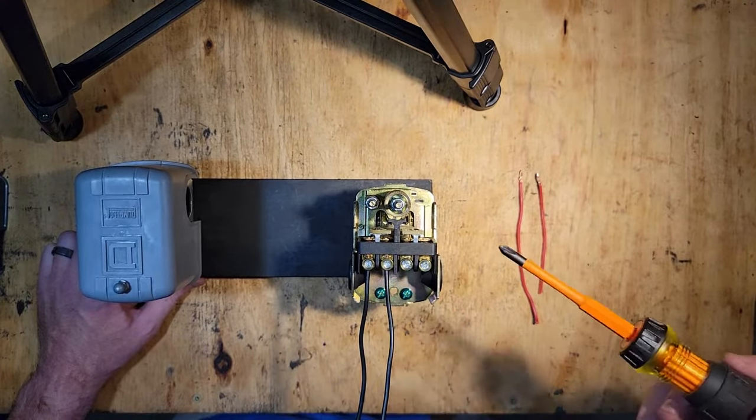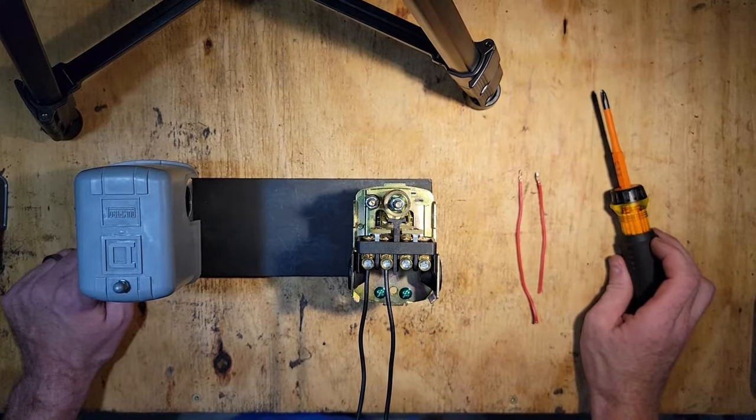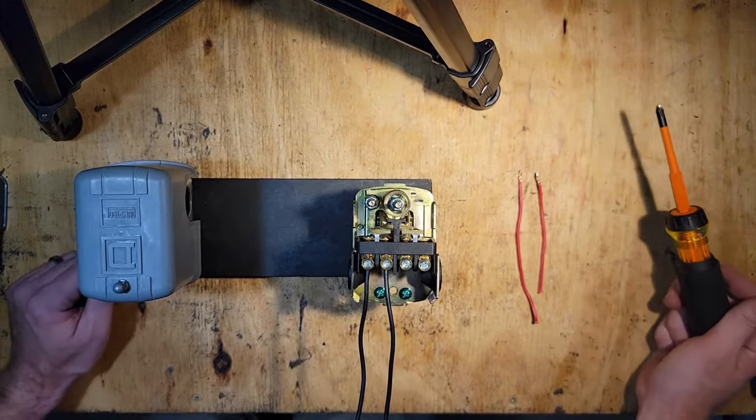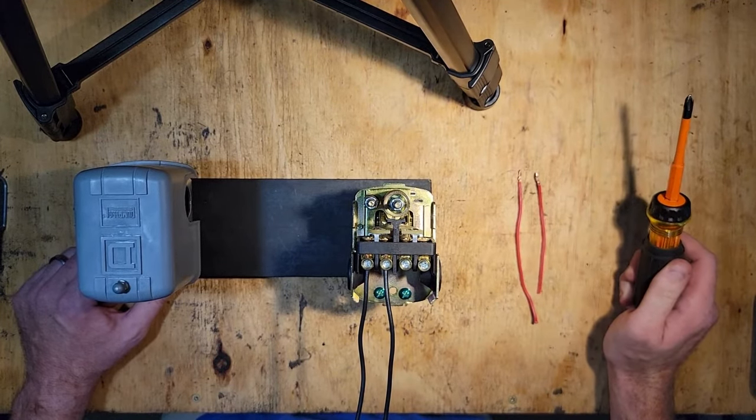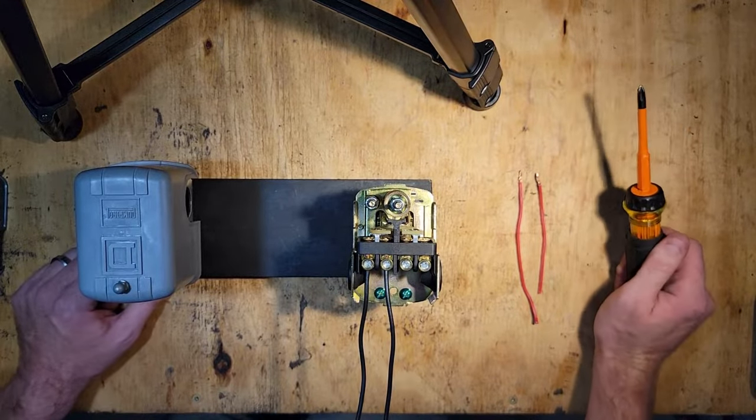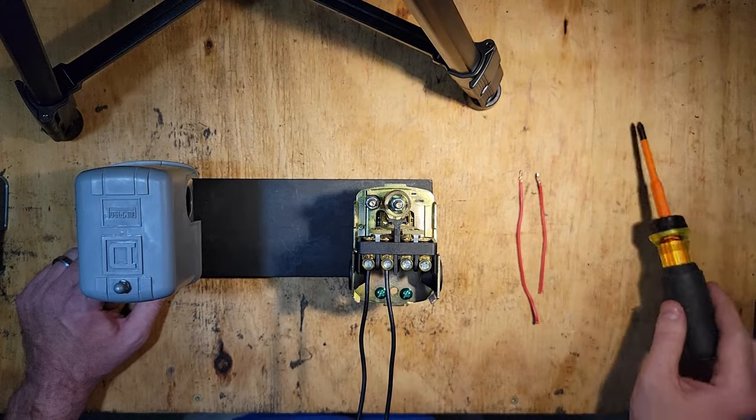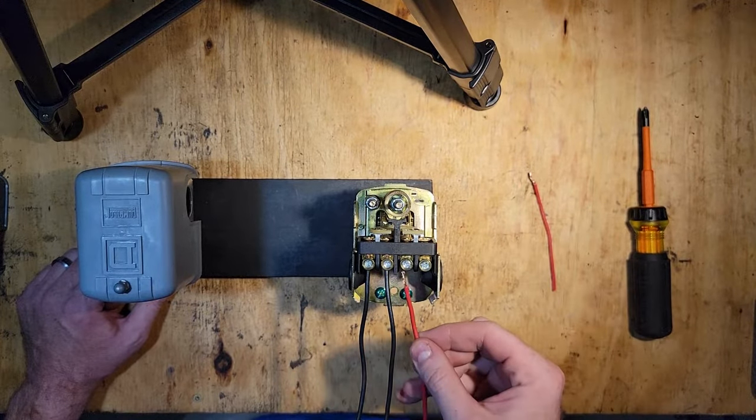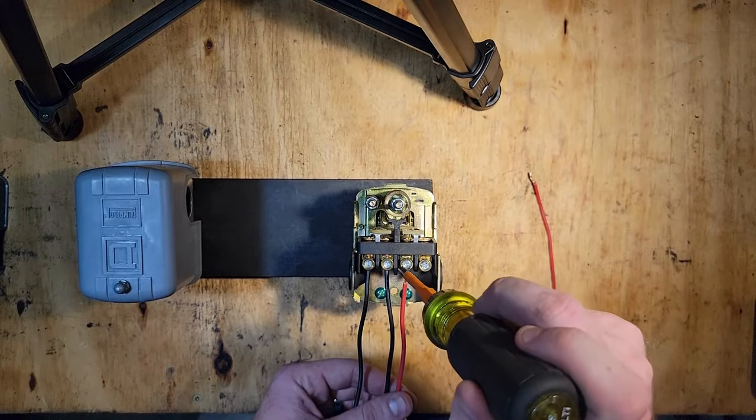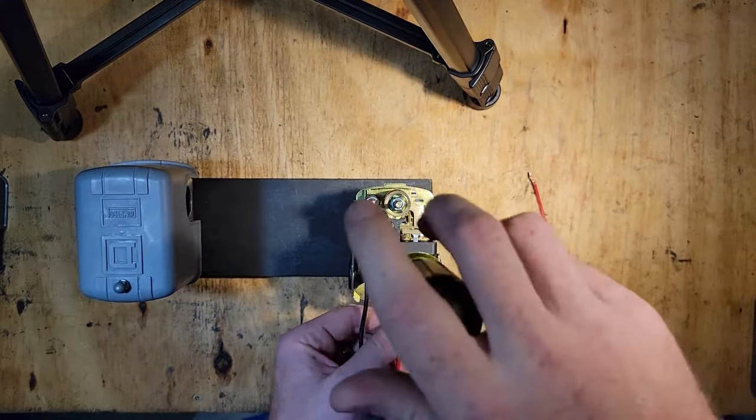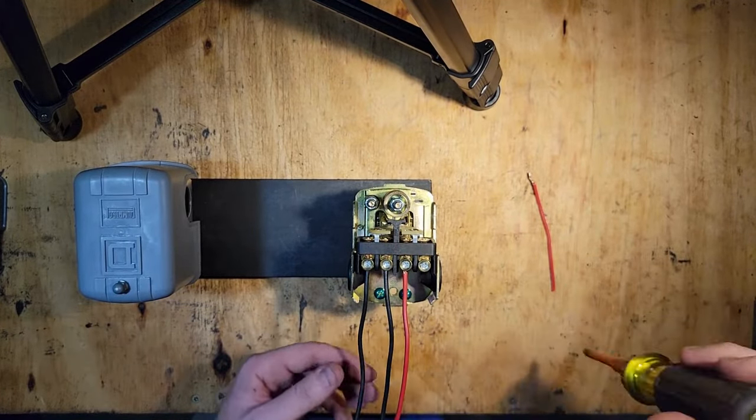Now if you have a control box that does not have the SW terminal, then the switch will function as a way to break the incoming power from your breaker. So in that situation, you're going to have four sets of wires in total. One set of wires is going to be the incoming from your breaker into the switch.